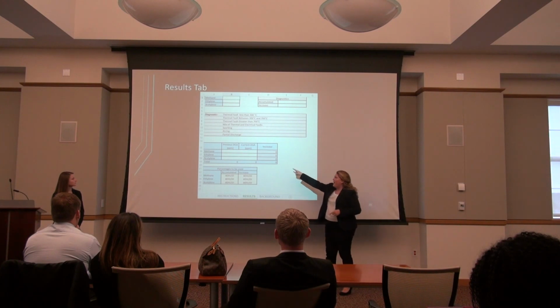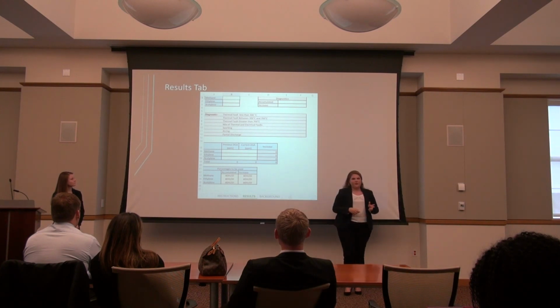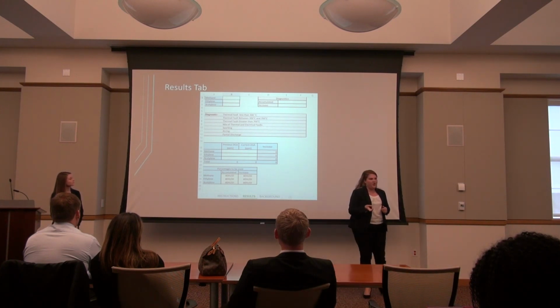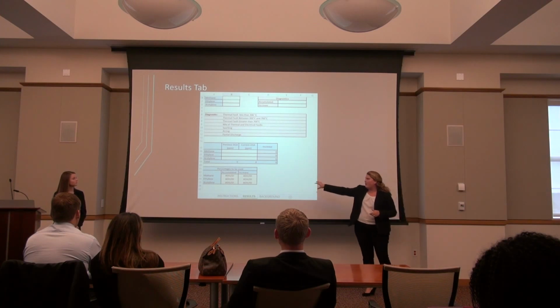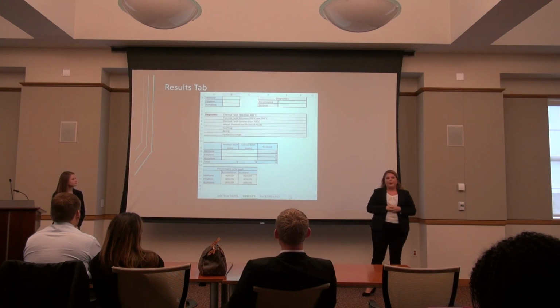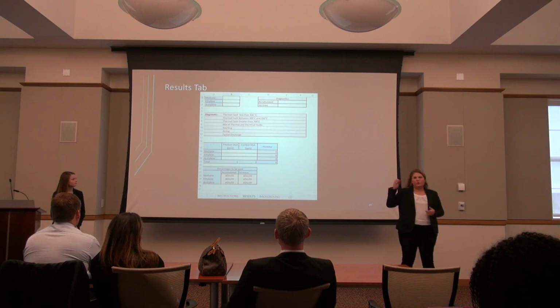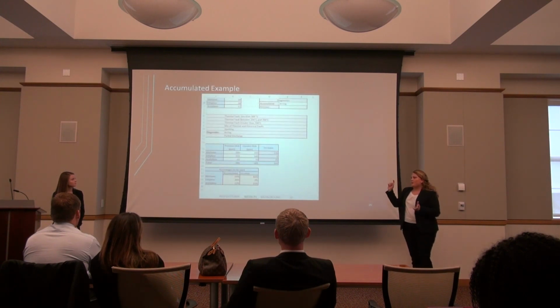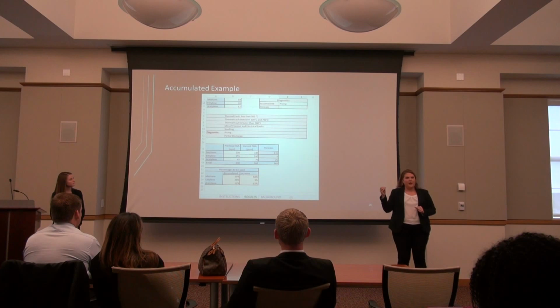They can put in the previous DGA results and also the current DGA results, and it'll calculate on the bottom yellow area the percentages that they can then input at the top. Something important to note is that wherever the diagnostics label is, that's the problem that is happening. It'll automatically move depending on the labels to indicate what the problem is.